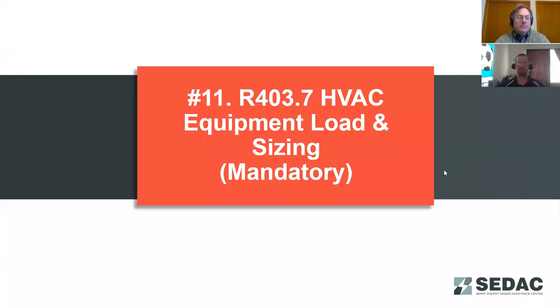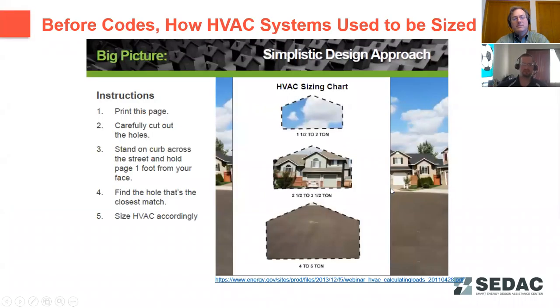Moving on to HVAC equipment load and sizing requirements. This is a fun example of something that Ryan has said he's actually seen someone use. You would hold this card out in front of your face, line it up on the front of the house from across the street, and match the front of the house size to the closest size on this card. It didn't take into account the depth of the house or anything like that, but that's how they used to size HVAC equipment.